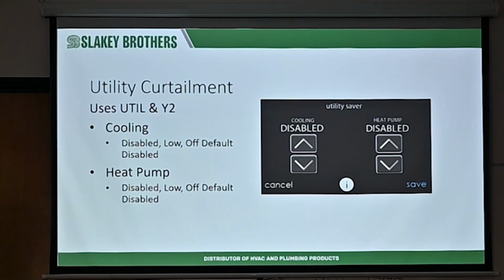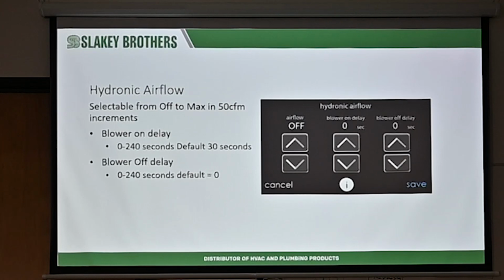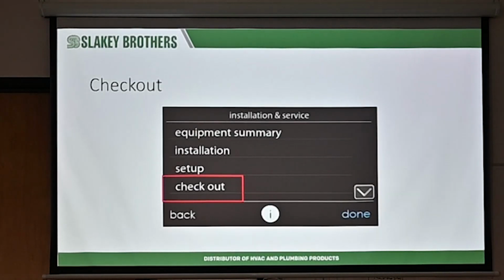There is a little accessory, a little bit of wiring you do on the outside, just a quick little wiring to the outdoor unit. You enable it, and when it gets that signal from the electrical company to shut down the condenser for a little bit, it'll do it. It'll do it safely without any fault codes at all. So it is there as an option if you ever run across that. Again, if you're doing hydronic, you're setting up different accessories, so you've got to tell it how to do the airflow there if you do that.